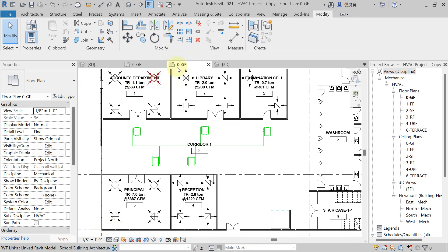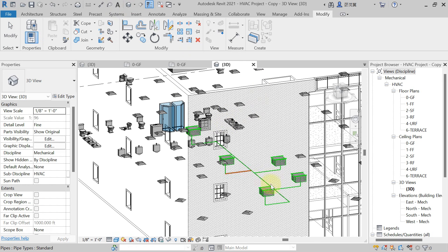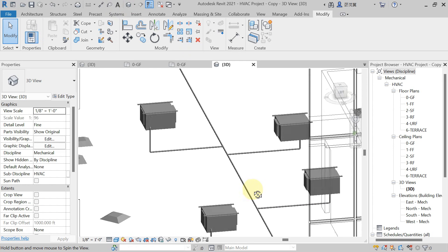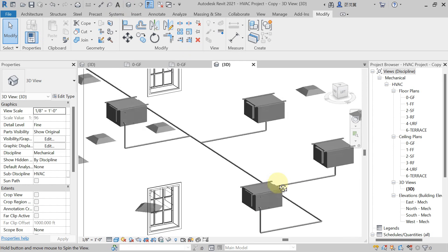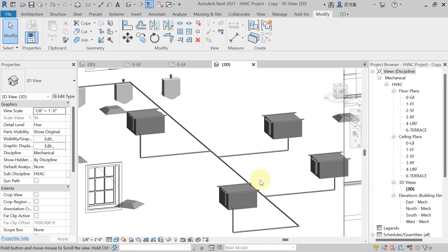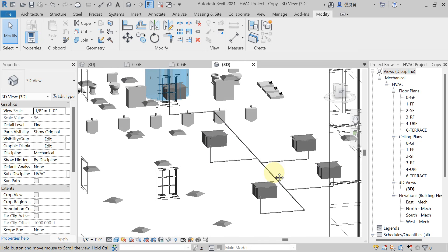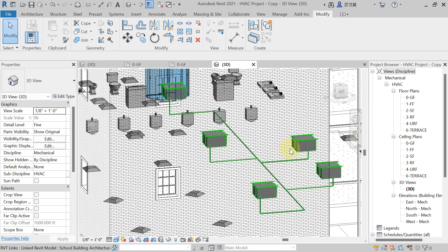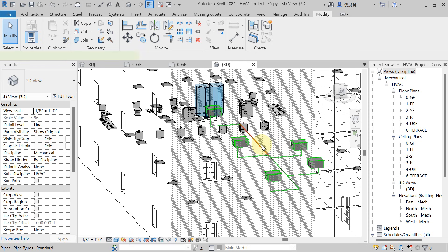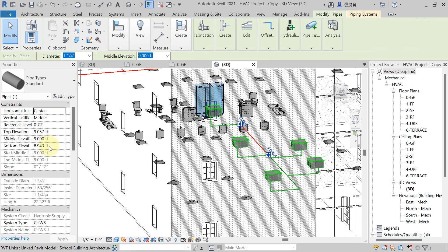Now the pipe layout is created. If you want to see the double line diagram, hit on Fine, then come here in 3D to see the routing we have drawn. This is our chilled water supply pipe. The problem is that the false ceiling is at 10 feet, but the main pipe bottom is showing 8.943 feet, so we have to run the chilled water supply above the false ceiling.